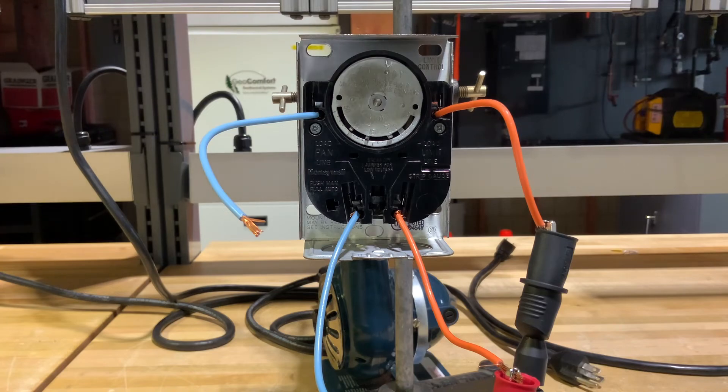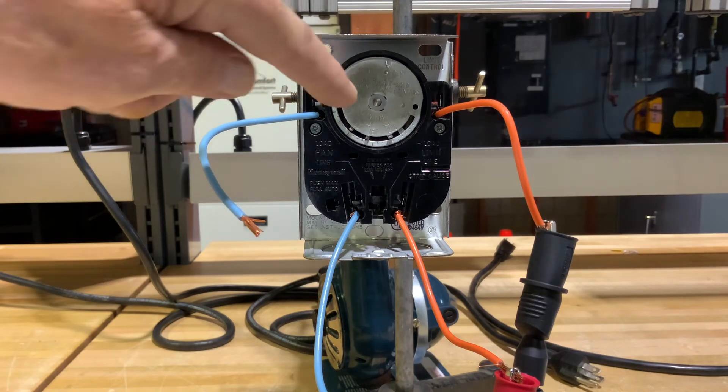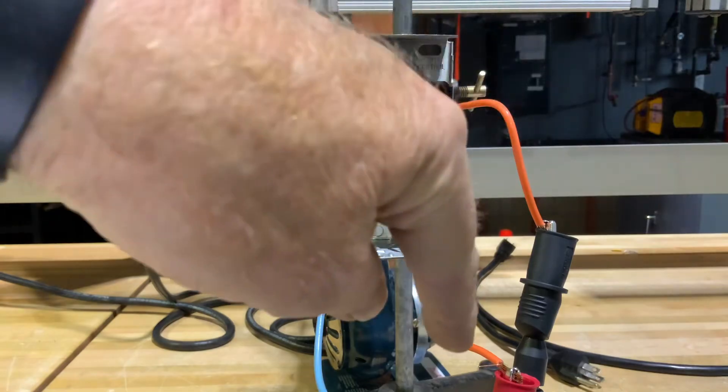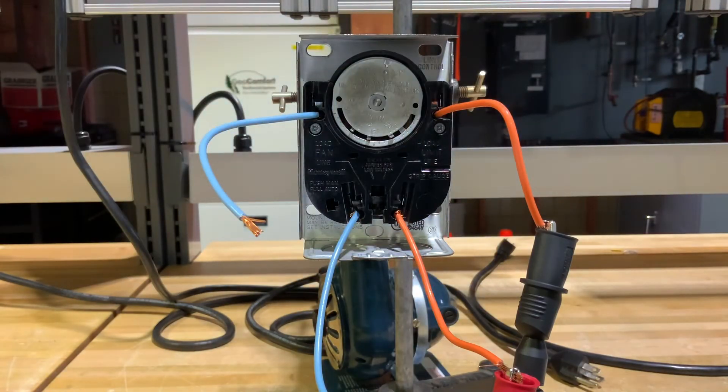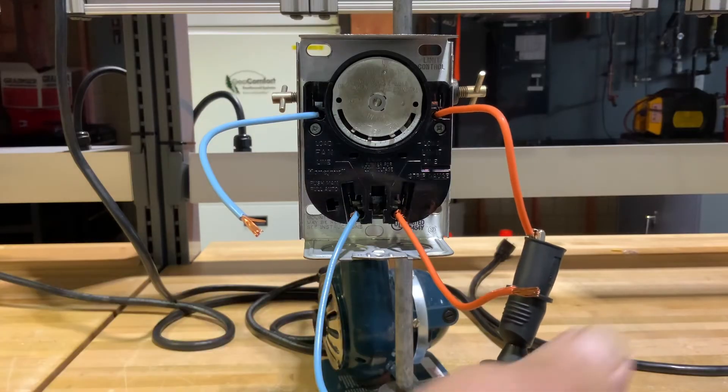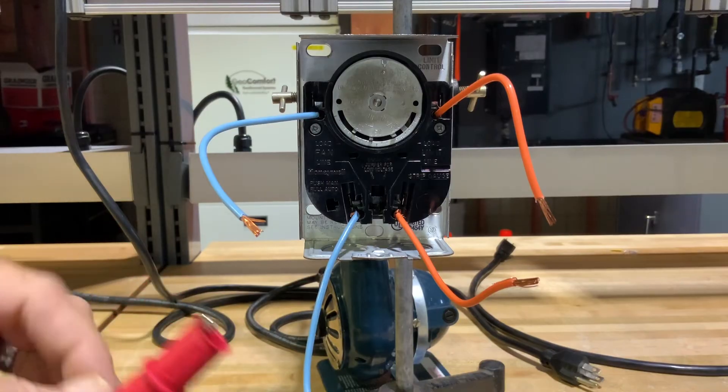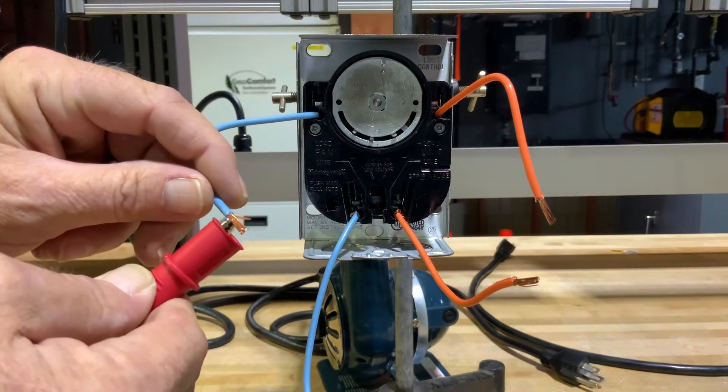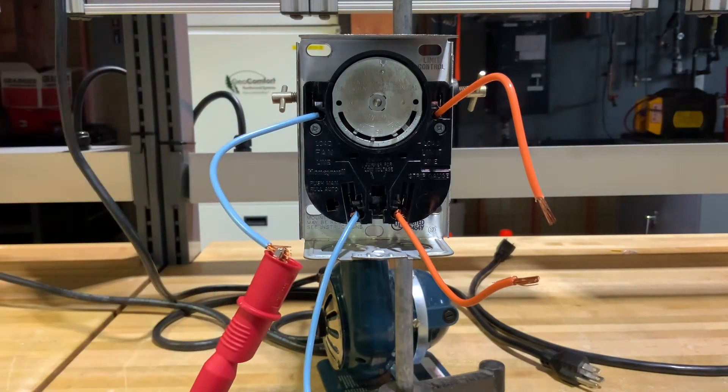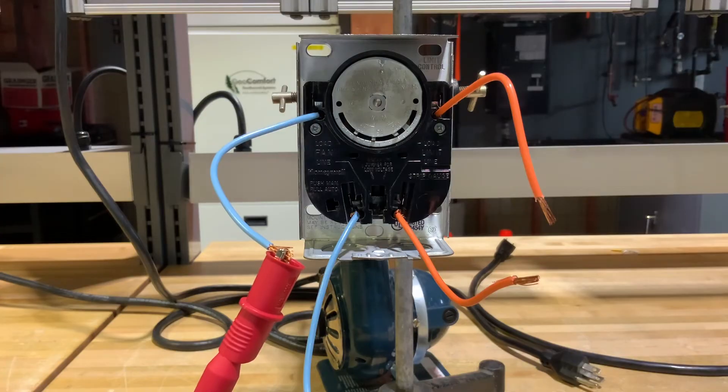So that thing's starting to cool down. We've cooled down enough now our limit switch is made again, so now we're sending power to that primary control unit. We've even cooled off enough that our fan shut off.